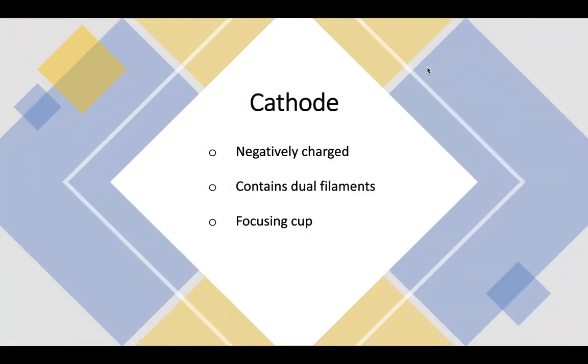The cathode is the negative side of the X-ray tube circuit. The beginning process of X-ray production and the source of electrons, electrical current passes through the cathode first and then to the anode to eventually convert into X-rays. It includes a dual filament and a focusing cup.